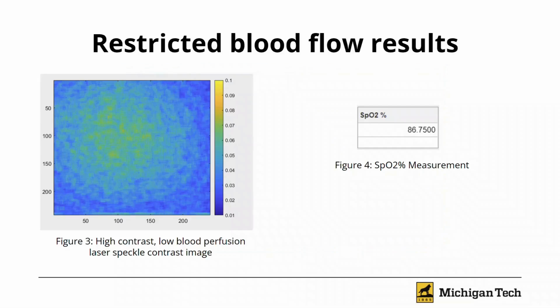The output from the probe shows a contrast image and an SpO2 measurement. The contrast image gives an indication of blood flow. Blood flow causes the speckle image to become averaged out over an exposure time, decreasing contrast. A lack of flow will produce an image with higher contrast, shown in the color yellow in the image.